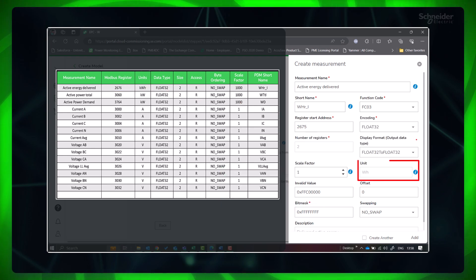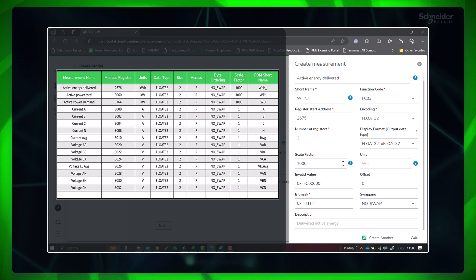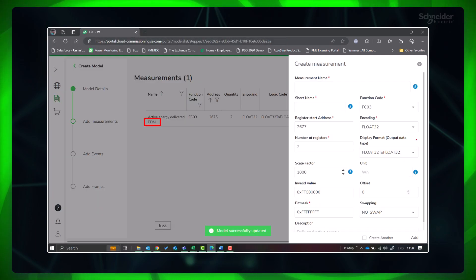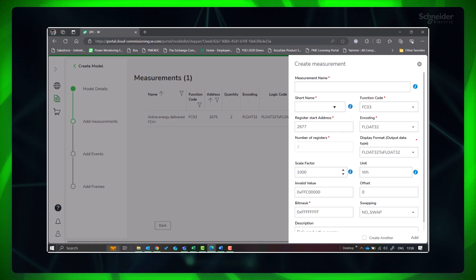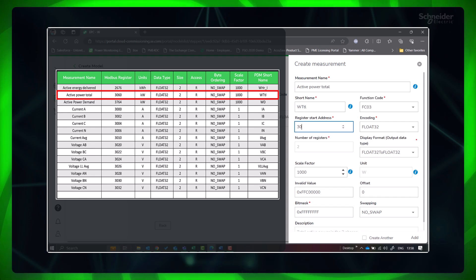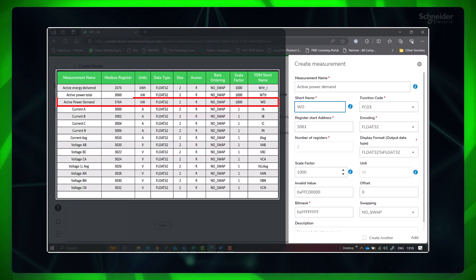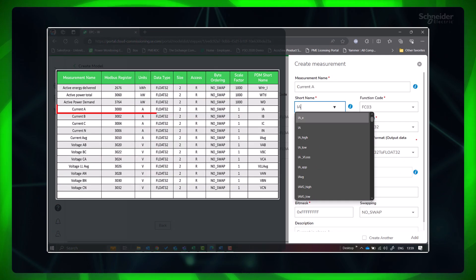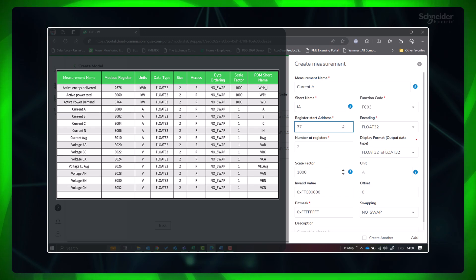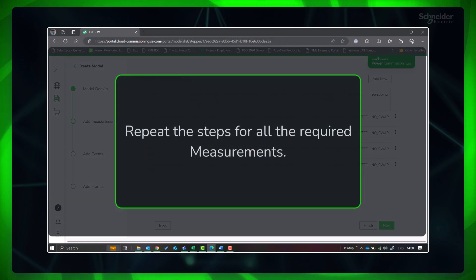Provide the data type as encoding; other fields are automatically populated. The register start address will be one less than the register number. Here in the portal, the unit corresponding to this measurement is Wh, but in the device Modbus table it is kilowatt-hour, so provide the scale factor as 1000. Click 'Create Another' and click Add. Make sure the PDM tag has appeared in the added measurement. Repeat the steps for the next measurement, active power total. If the unit is the same in the device Modbus list and the portal, then the scale factor will be 1. Repeat the steps for all required measurements.